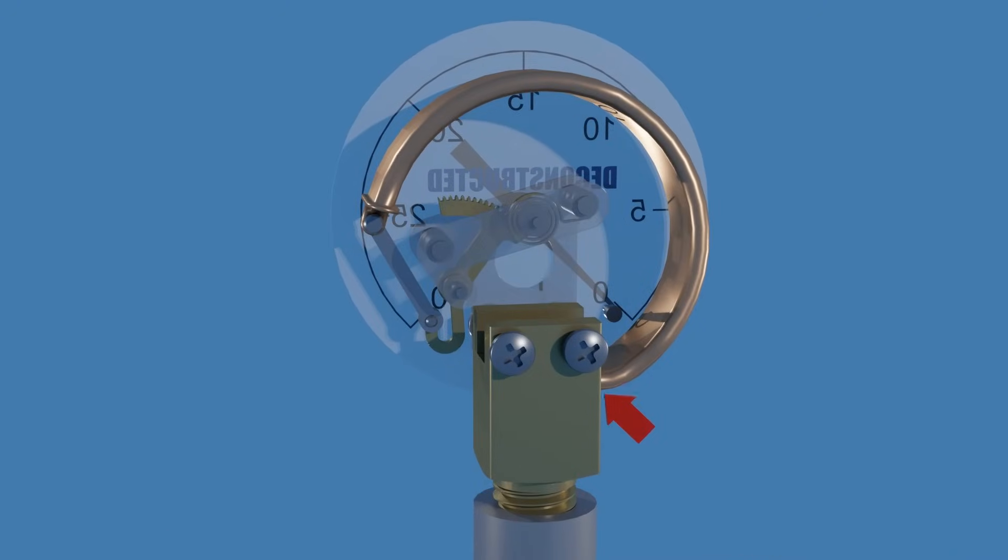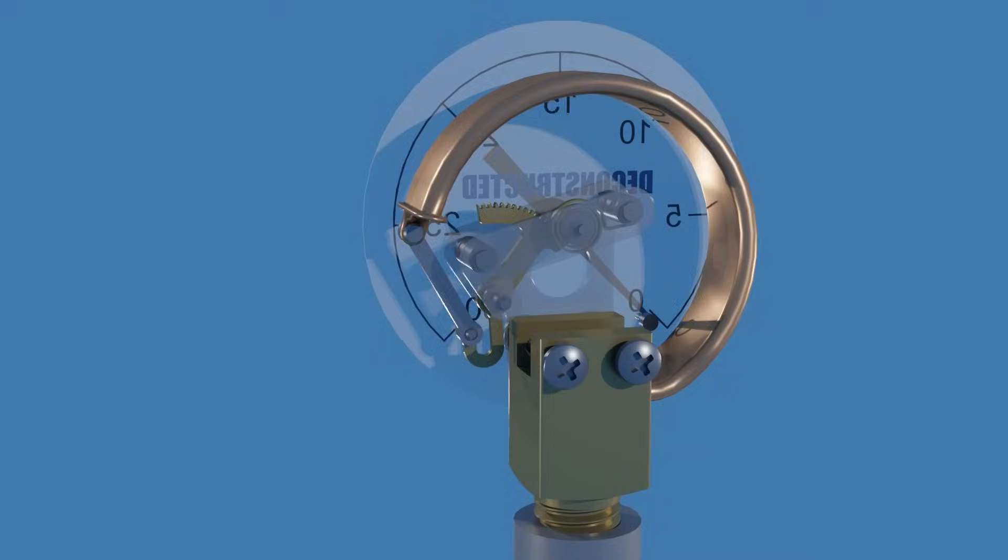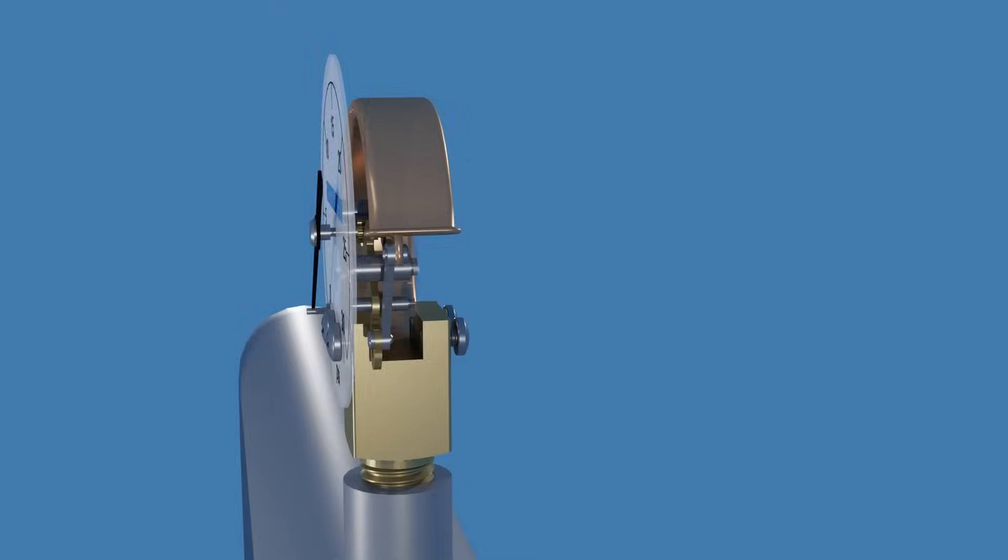The fixed end of the Bourdon tube is mounted to the socket base, and the moving sealed end is connected to a mechanism that translates the small deformation of the tube into a rotary movement for the pointer.